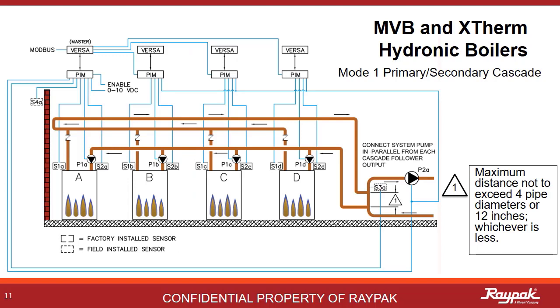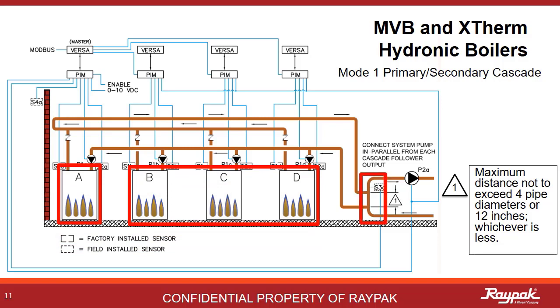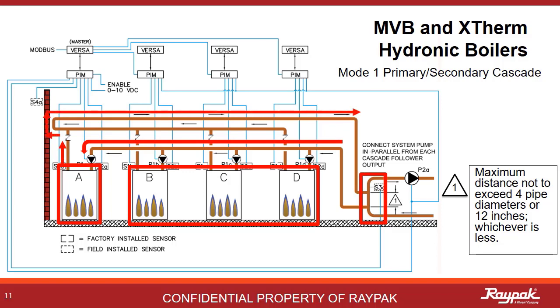This is a Mode 1 cascade system. Boiler A on the left is the master boiler, and boilers B, C, and D are the followers. All of the same decoupler concepts apply, only now they apply to the whole cascade. An important part of plumbing boilers in cascade is to use reverse return logic. The first boiler out to the loop is the last boiler to receive water back from the loop.